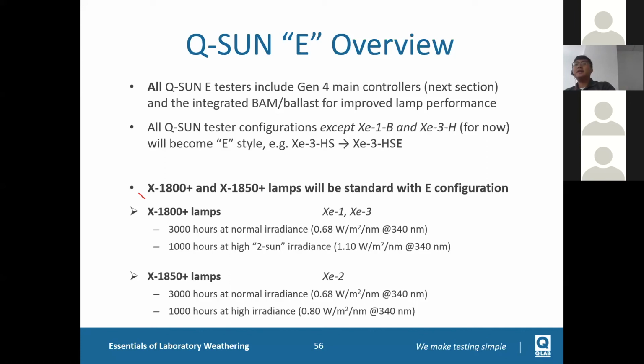The second thing is, if the customer uses the normal irradiance set point, like 0.68 or lower, we will give 3,000 hours warranty for the lamp life. Remember, in the past it was 1,500 hours, so we doubled the lamp life. Of course the price of the lamp will increase by 50%, but the life of the lamp increases by 100%, so this helps customers reduce their operation cost.